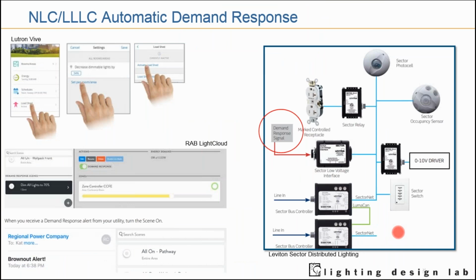On the right-hand side, you can have a typical network lighting control system, where either at a main load controller or at separate specific load controllers at a gateway or hub, they can listen to analog contact closure or dry contact signals to turn a subset of lights off. Or they can be programmed so that when a signal is received, they know what lights to dim or turn off.